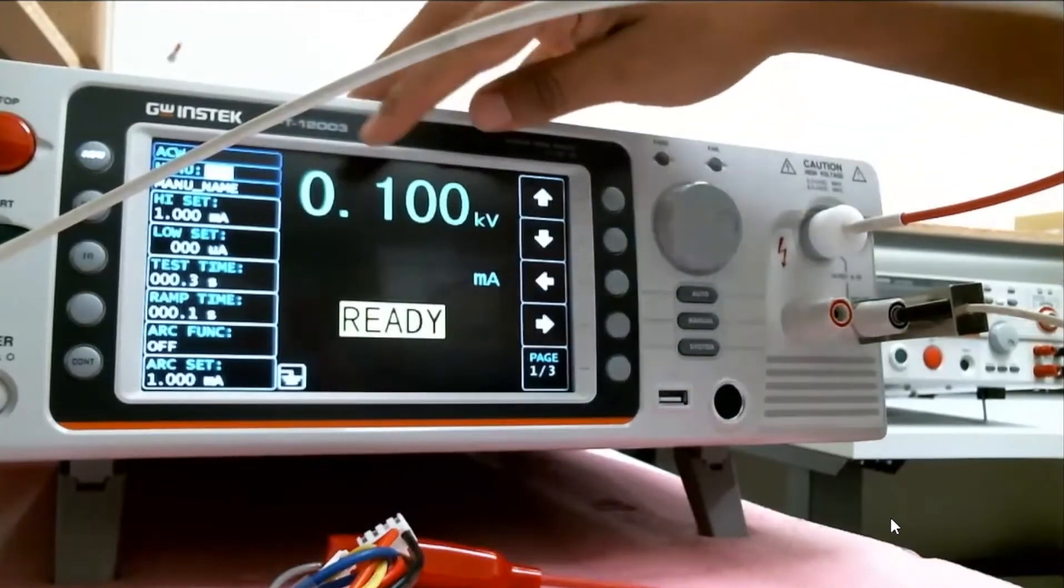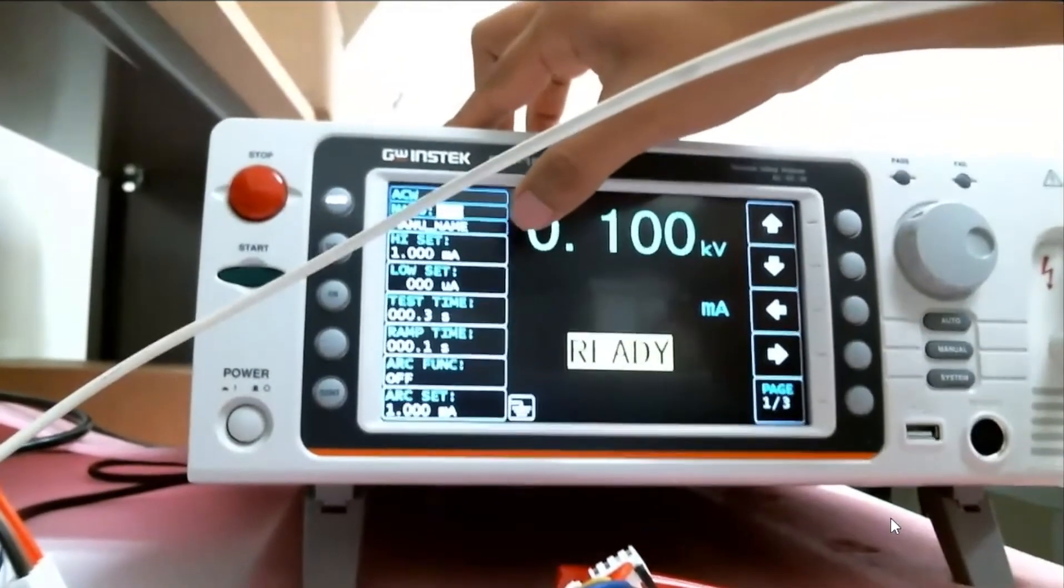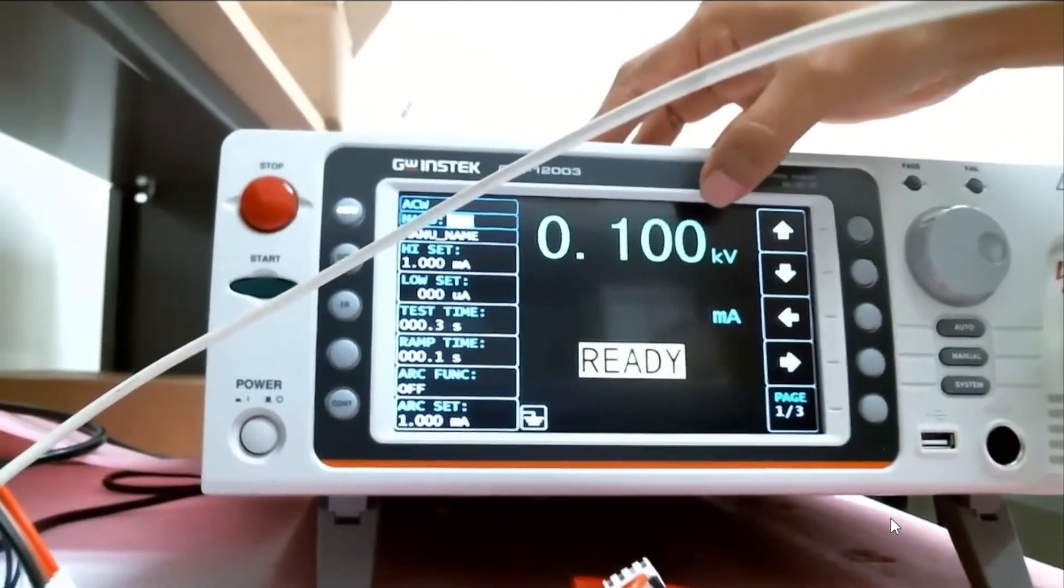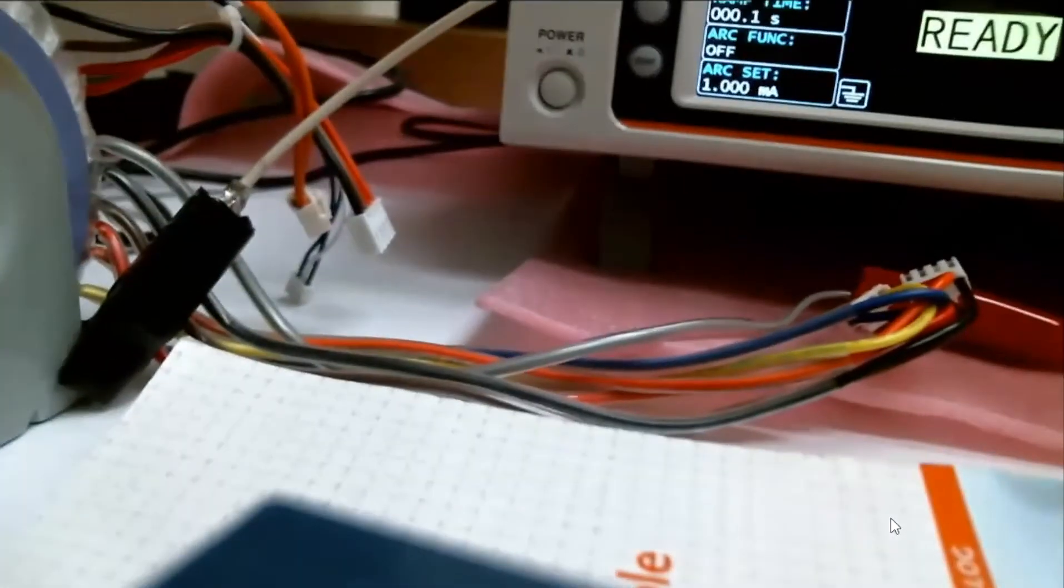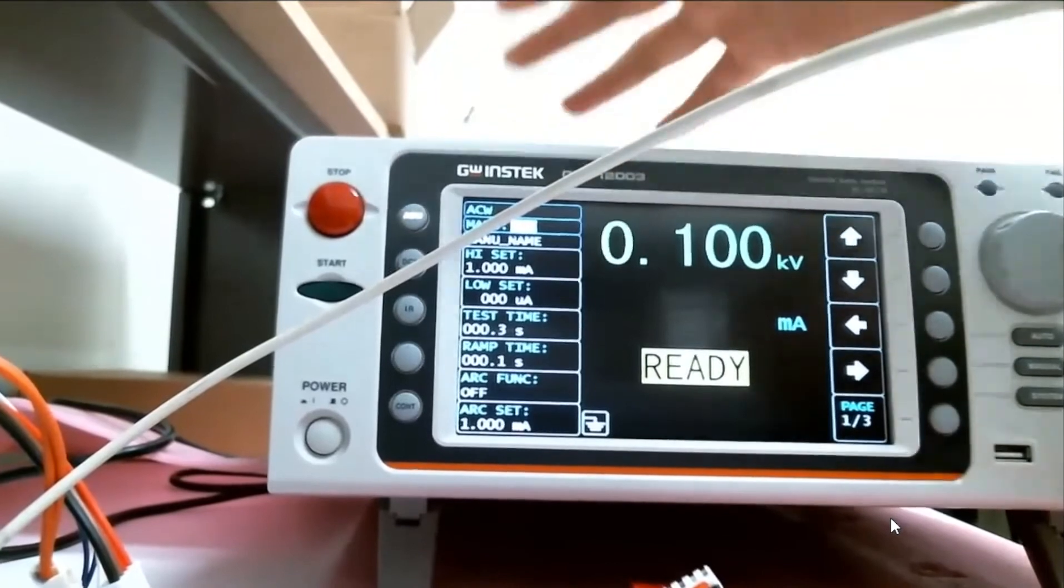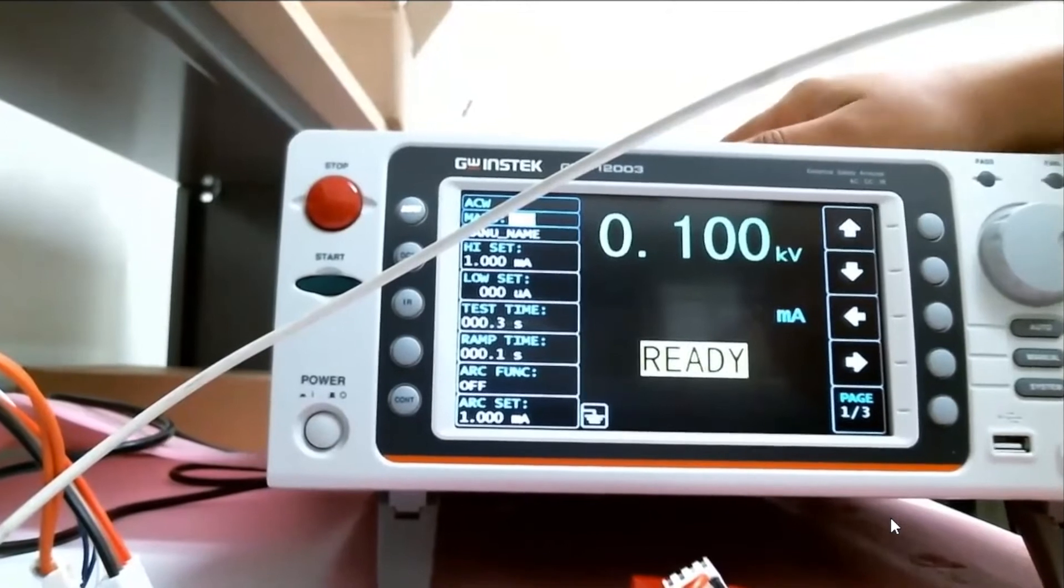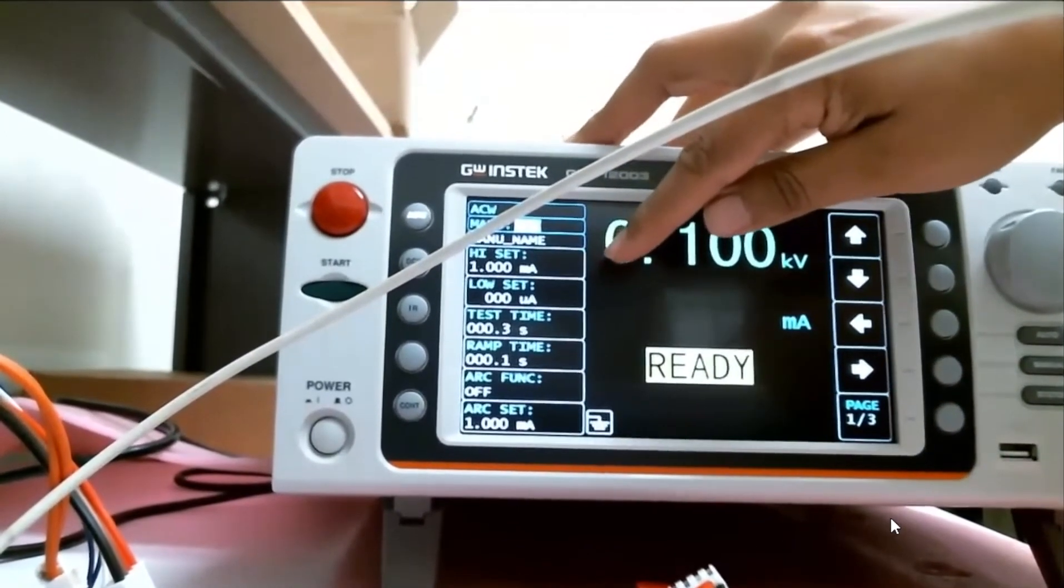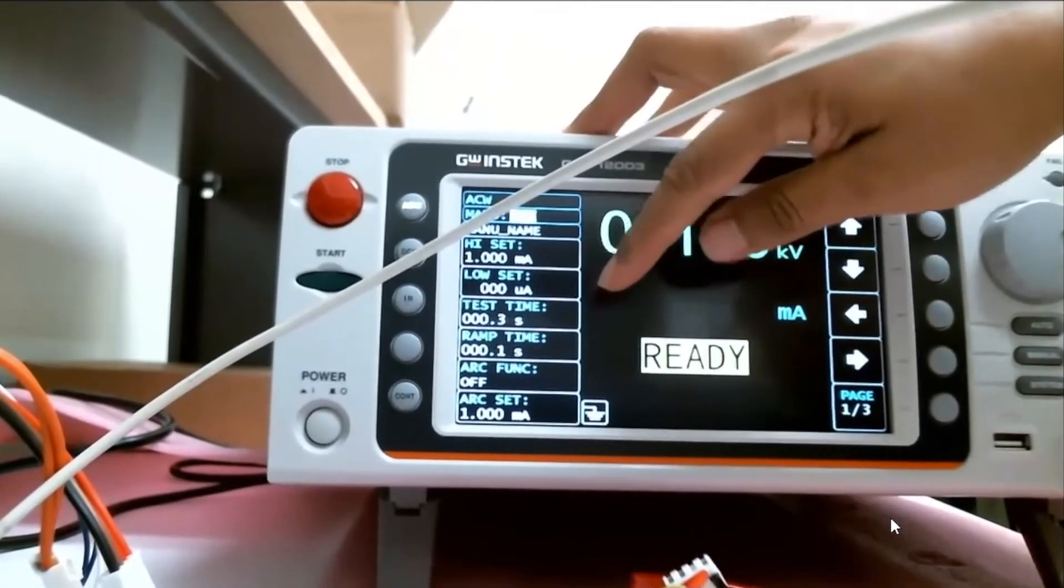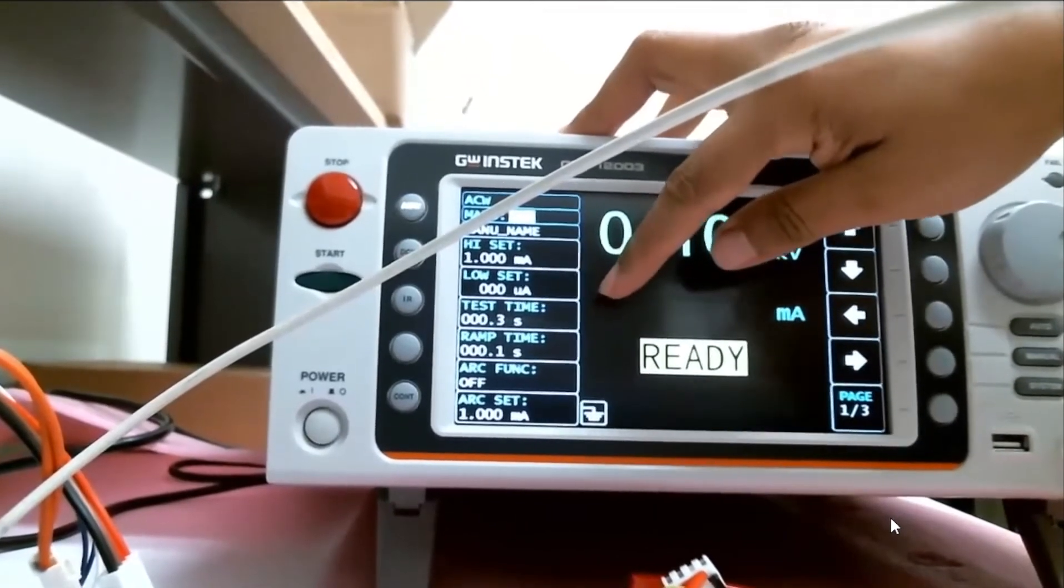I've already done the setup here. My limit, so what I'm telling the instrument here is I'm going to inject 100 volts of potential into this transformer, this transformer winding. And my leakage current can be no more than 1 milliamp. It varies from standard to standard, manufacturer to manufacturer, but these limits are kind of set by the quality department of each manufacturer. What I'm telling you here, my low set, we won't talk too much about that, but I'm going to have it at zero.